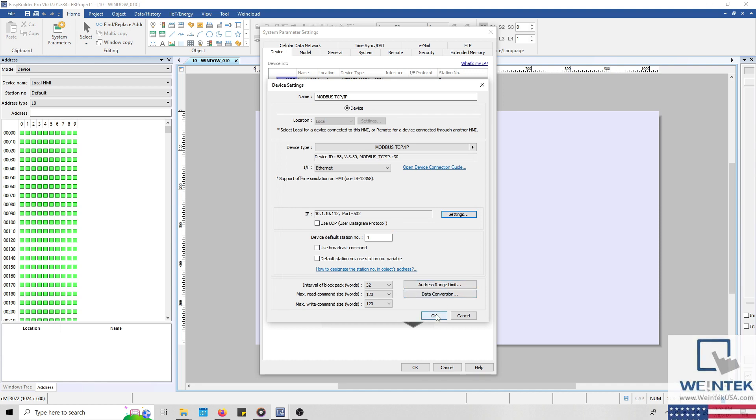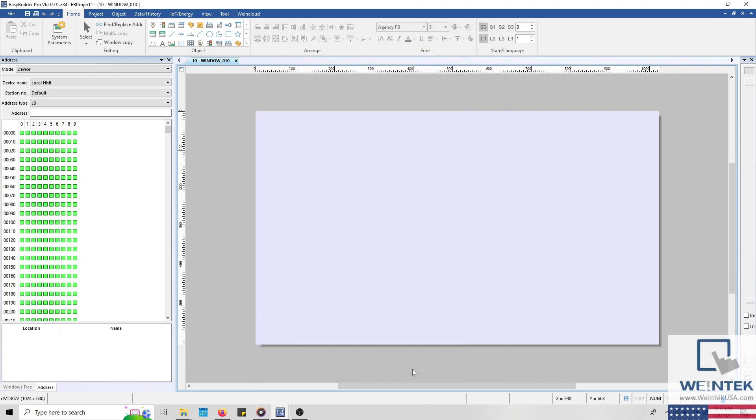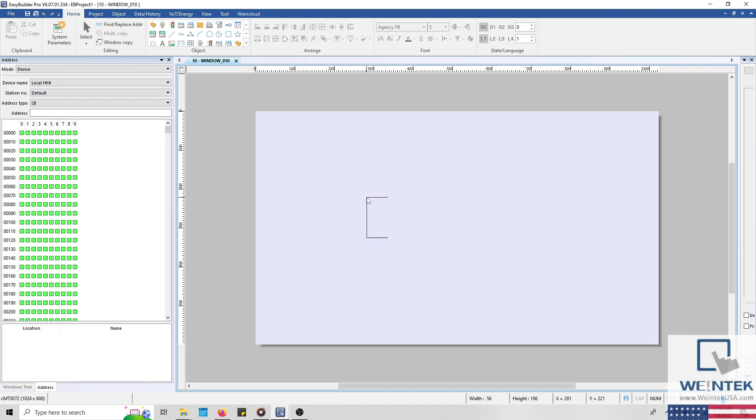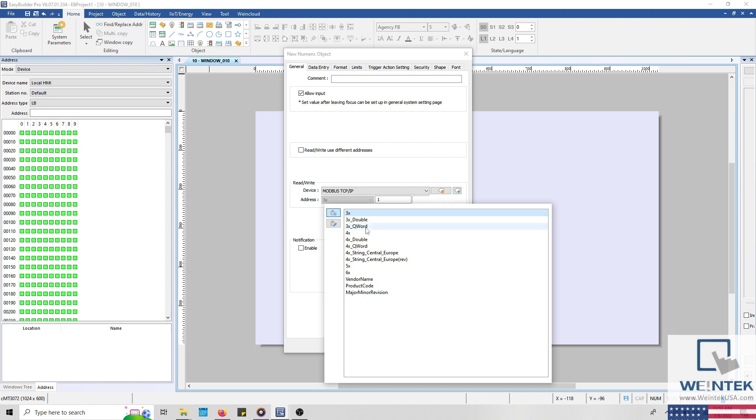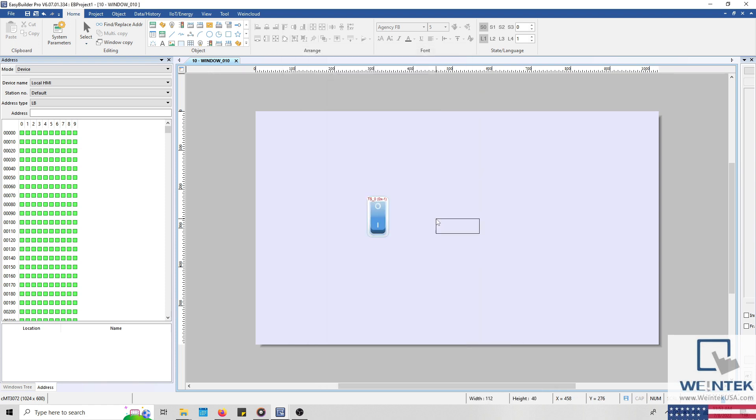When finished, I'll click OK to add this driver to our project. Once again, I'll add a toggle switch. However, this time we'll address the toggle switch to 0x1. This corresponds to LB0 within the HMI that was configured as a Modbus server. We'll also add a numeric object addressed to 4x1. This address corresponds to LW0. With that configured, let's download this to our HMI for testing.